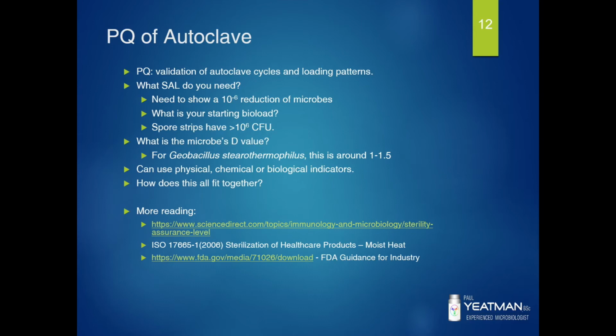Ideally, whatever the guidance says, that's what you want to do, as it's always great when you don't have to explain what you're doing to an auditor. So if you follow the guidance, then there's no question marks as to why you're doing something different. You want to consider the microbe's D value. Typically we would use Geobacillus stearothermophilus, which is a spore former, and the D value of this microbe is 1 to 1.5.